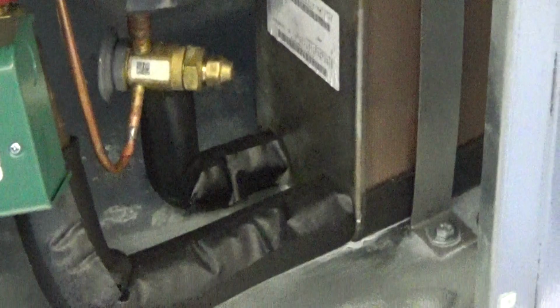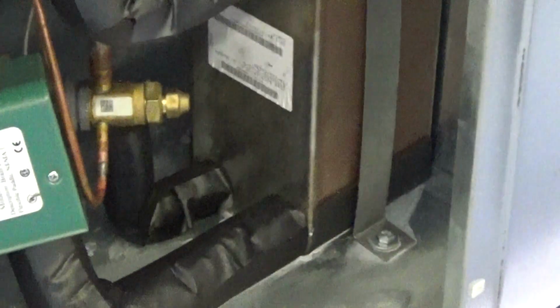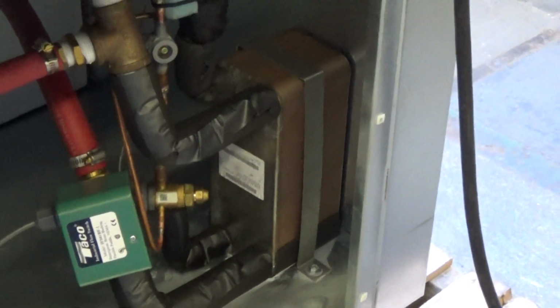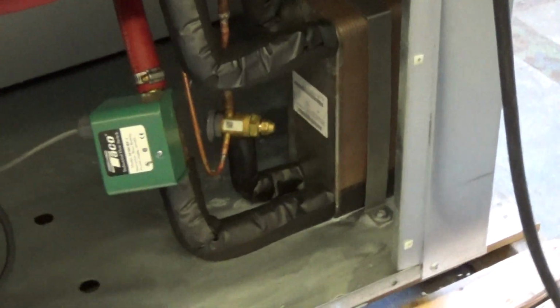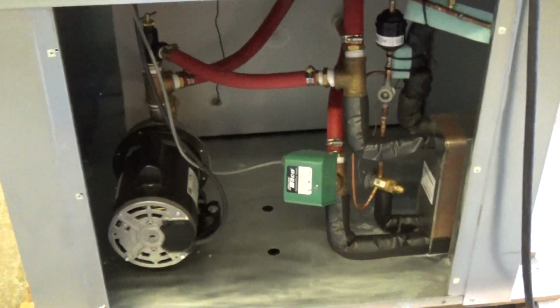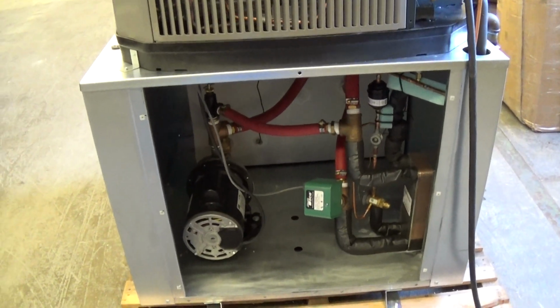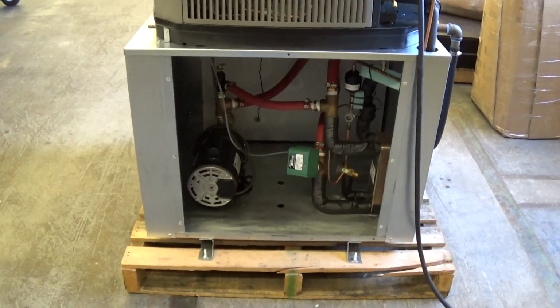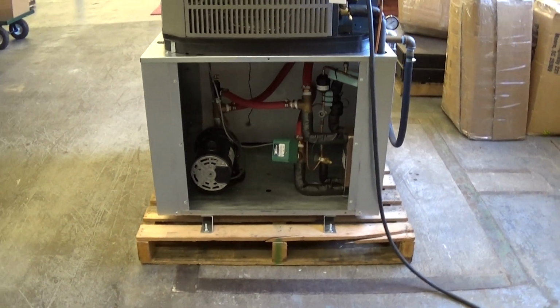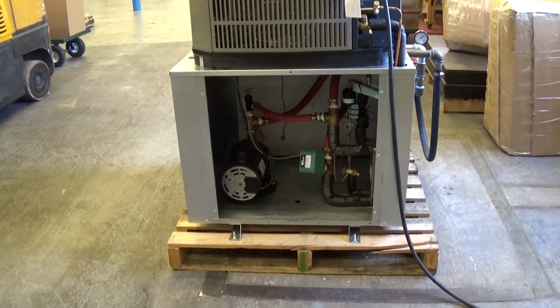We do have our refrigerant sight glass there. There's also our thermal expansion valve and our braze plate heat exchanger. Also on a lower temperature application, whether it's in a warmer climate, a colder climate, or if we're running lower temperature glycol, that would be insulated also. But again, I'm going to run it down to 25 Fahrenheit today just for the test, so it will get some frost on it. But again, this exact unit's going to go to an application out in the field where they're running substantially warmer than that.